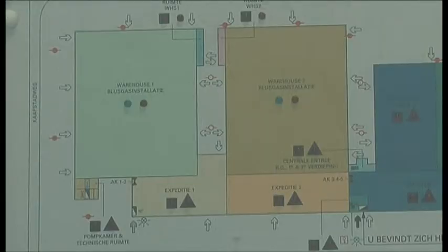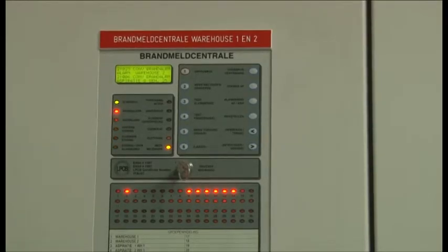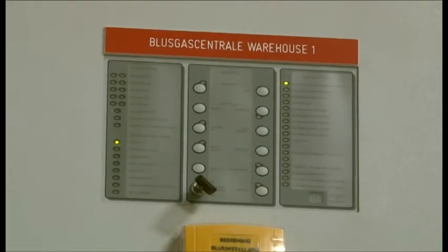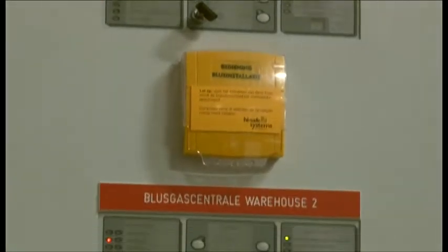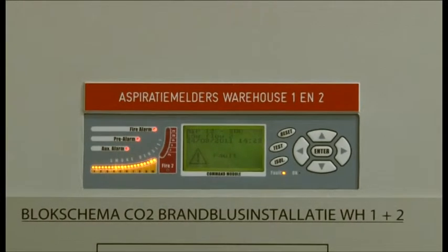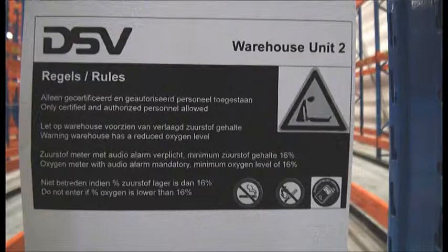We will test the installation today. A number of lights blink on the fire panel if the alarm goes off elsewhere in the building. There are visible and audible warnings outside and within the halls. You must evacuate immediately because the oxygen percentage will be reduced considerably. After an extra loud alarm, CO2 will be injected.